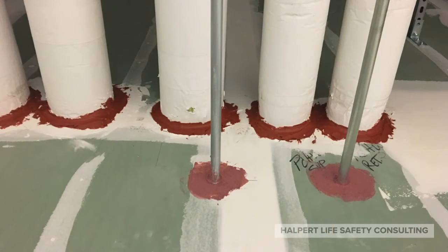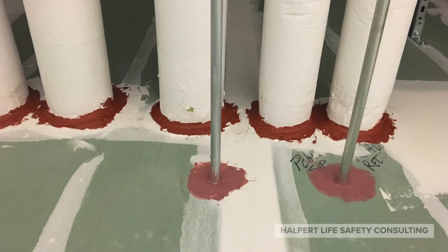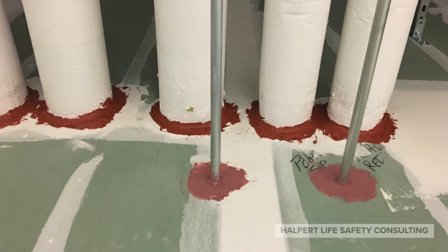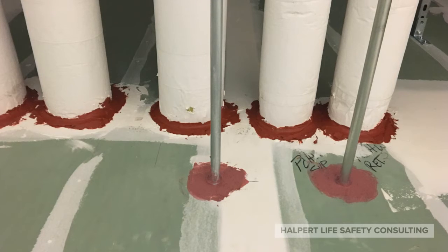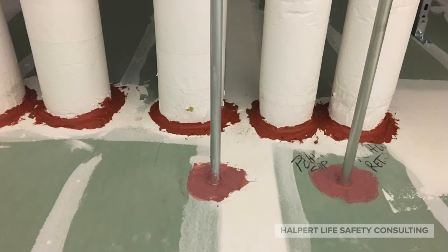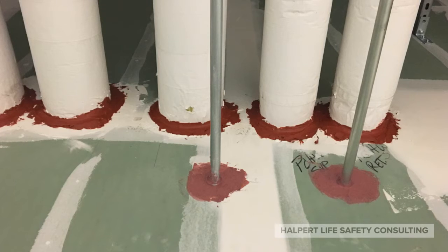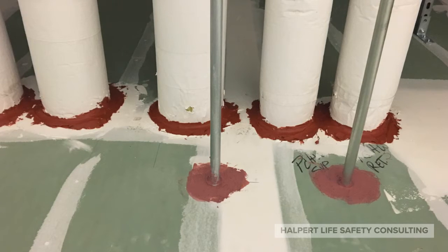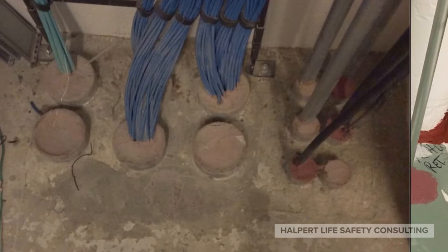Here we have two different conditions. Since this is a gypsum wall, we know that we have a WL detail for a framed gypsum wall. The conduits will be the 1000 series detail and the insulated pipes will be in the 5000 series detail. That was pretty simple, wasn't it?